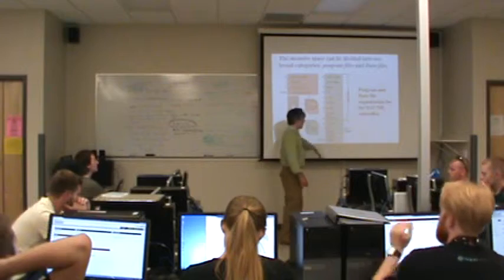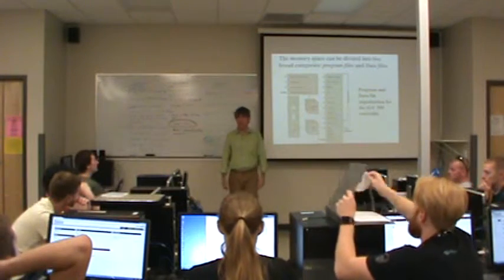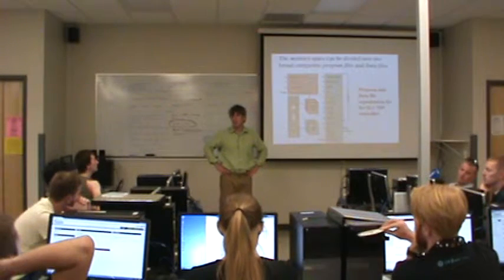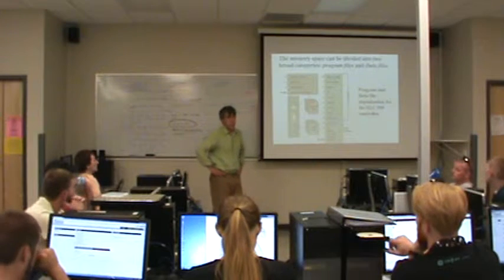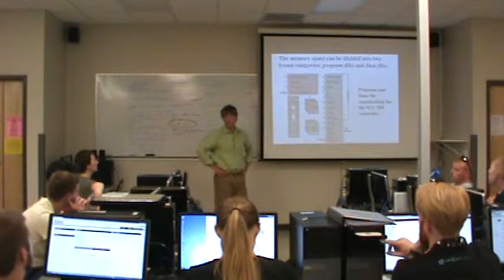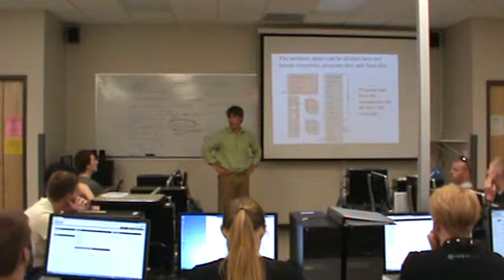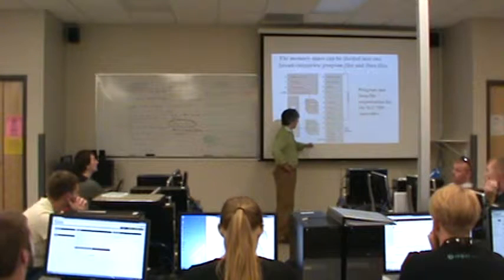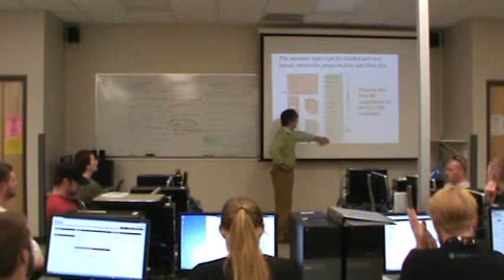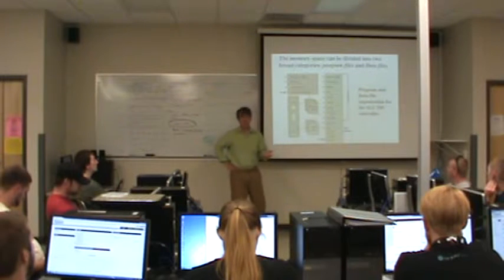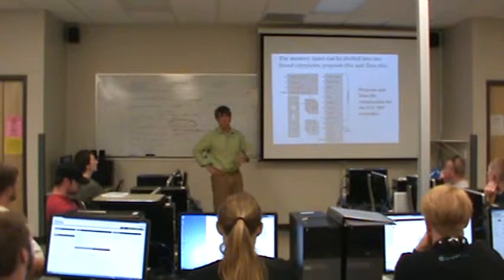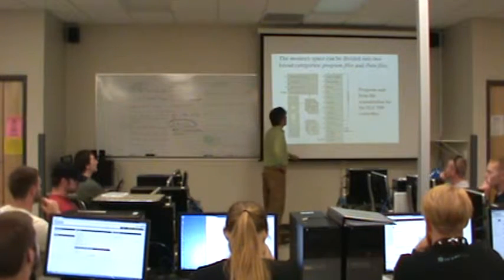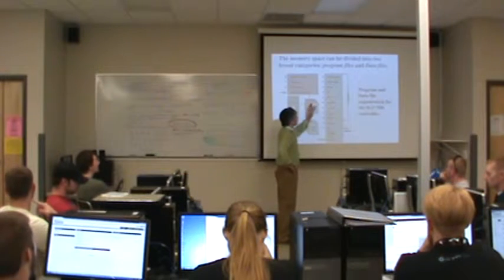Now there are typically files beyond this. Typically there's at least up to file number 255. Not surprisingly, most things in a PLC are based on integers or multiples of 2. So if you think about it, 256 is 2 to the 8th power, right? So 255 is 2 to the 8th power less 1. Anyway, the files beyond file 9 are typically files that you can set up to be whatever you want. If you need more timers, you can make another timers file. If you need more memory, you can declare it, define it, and use it essentially as another integer or bit file, whatever you need.